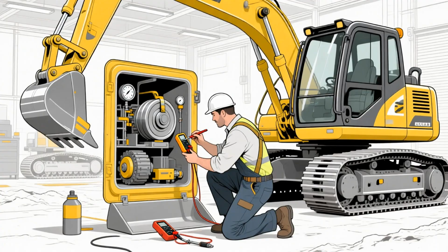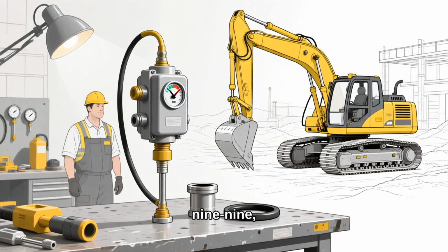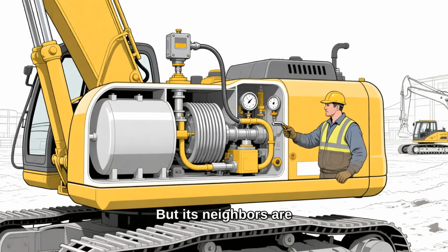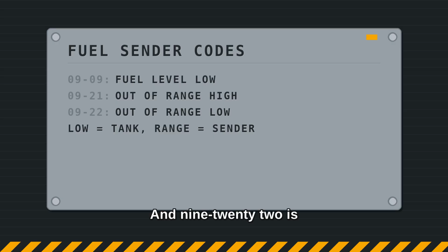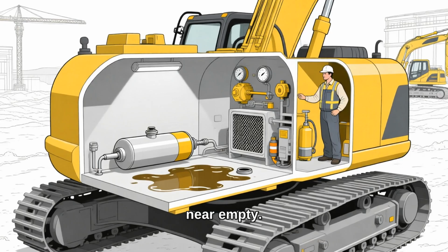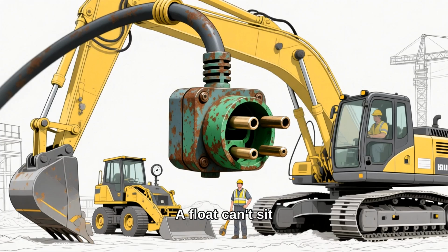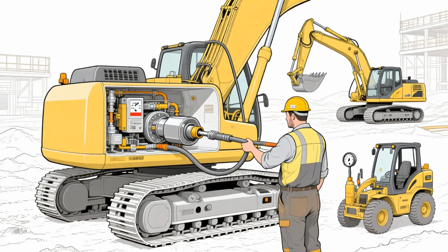So let's start cheap. Cheapest code on the machine, 99 fuel level low. That one is exactly what it sounds like. But its neighbors are the interesting ones. 921 is fuel level out of range high, and 922 is fuel level out of range low. Out of range is a different animal than low. Low means the tank's near empty. Out of range means the sender is reporting a value that can't exist. A float can't sit below empty, so that code is usually a connector, a ground, or a pinched wire. Check the sender plug first. That's the difference between 5 minutes and a scheduled service call.